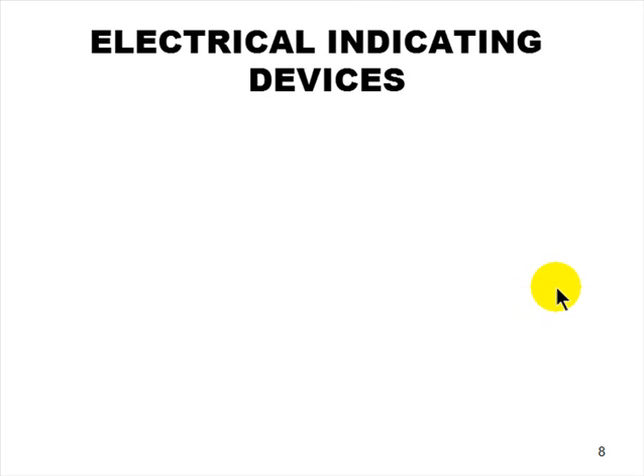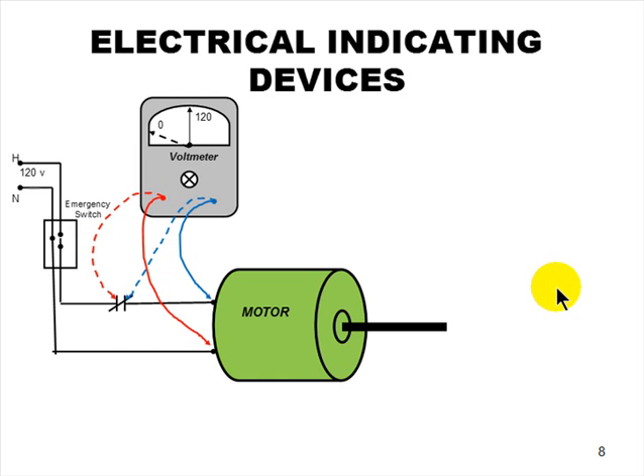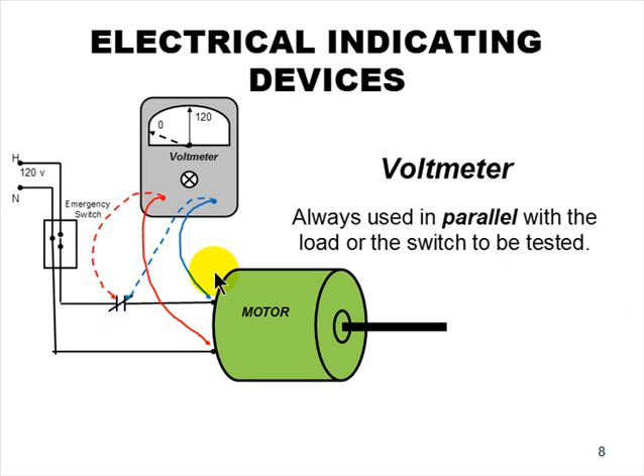Electrical indicating devices. What are electrical indicating devices? Things like voltmeters. A question on the test is going to be, how do you get a volt reading? You put a voltmeter on it. Okay, good. Now, how do you connect it? How is that voltmeter connected to this motor, and how is it connected to that switch? Well, it's connected in parallel. It's across the load. When somebody says put a voltmeter across that load, they mean exactly that, across the load, not in series with it. You put a voltmeter in series, you let the smoke out of the voltmeter.